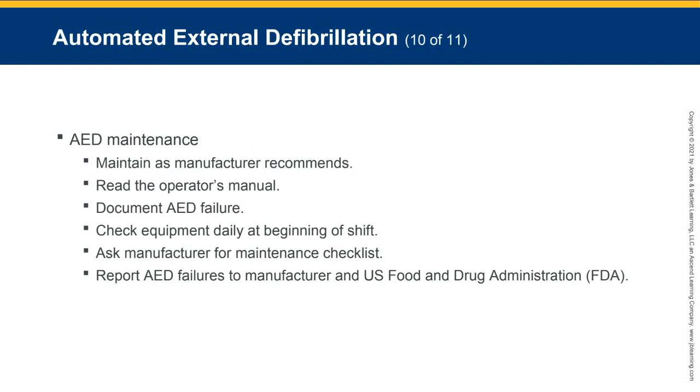Now, AED maintenance: maintain as the manufacturer recommends, read the operator's manual, document AED failure, check equipment daily at the beginning of shift, ask the manufacturer for a maintenance checklist, report AED failures to the manufacturer and the US Food and Drug Administration (FDA).